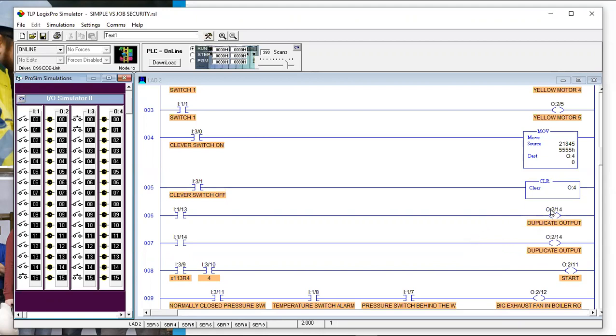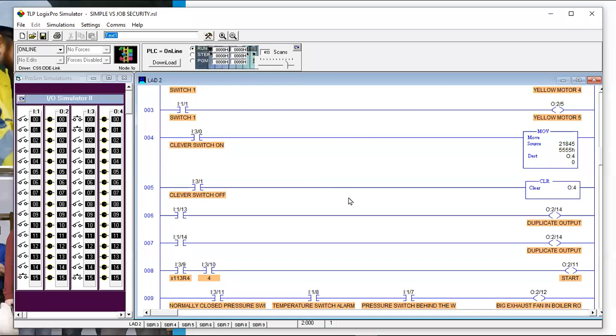Two ways around that: one easy way — if you plan to use a spare output, go up and search for it first to see if it's used anywhere in the program. That's the first step. Also worth knowing: if you're troubleshooting and you see an input instruction that's true but the output isn't, that's confusing. There are only a few ways this can happen.